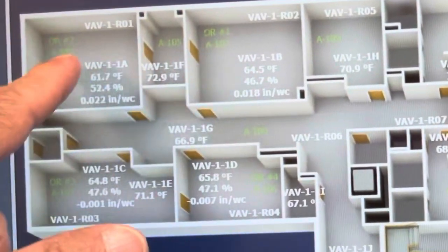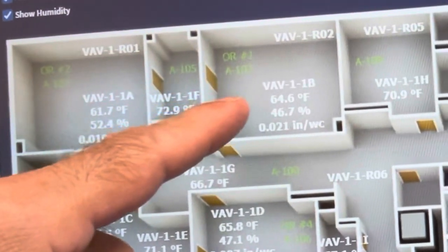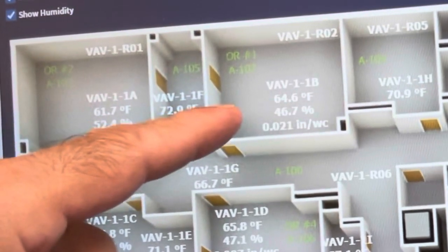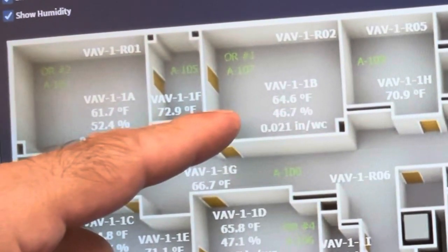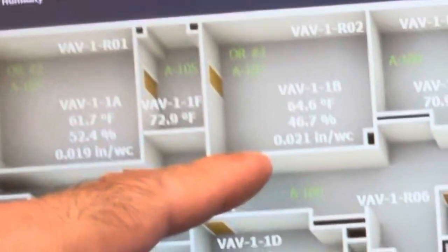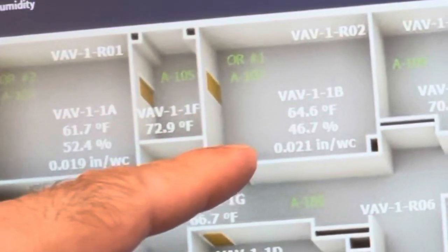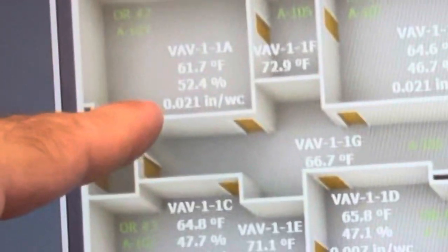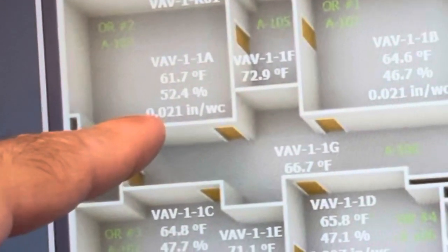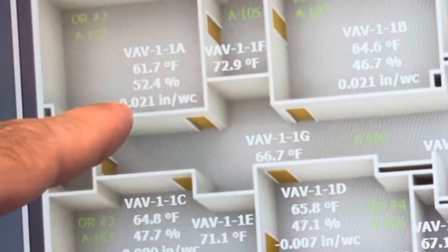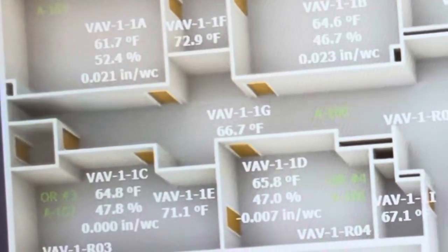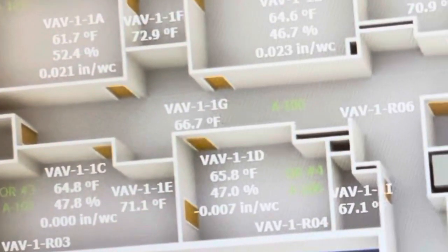Okay, I brought up the BAS and I want you to take a look at the room pressures. So this is operating room 1, this is operating room 2. In operating room 1, we've got a temperature of 64.6, relative humidity of 46%, and the room pressure is 0.02, which is the set point. Same thing over here, 0.02 inches, which is at the set point of 0.02. So the room pressures are much better, much lower.